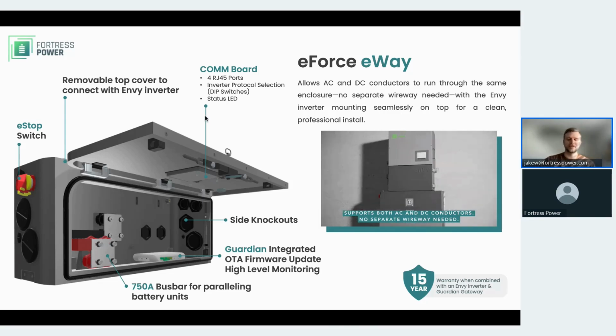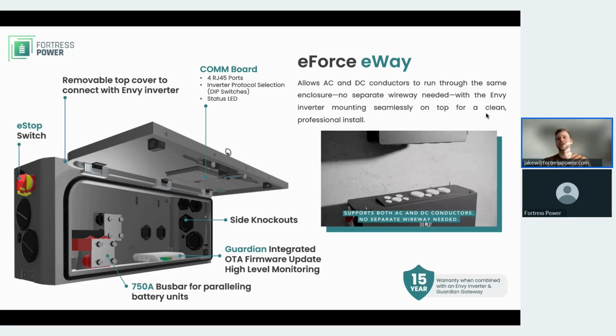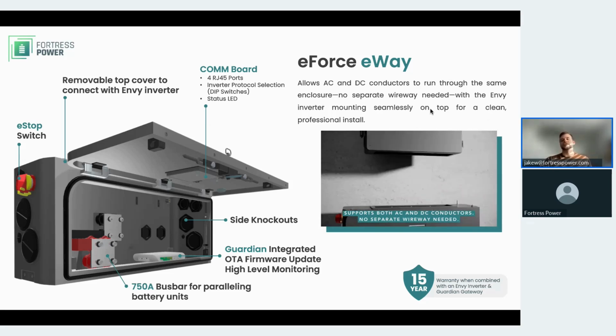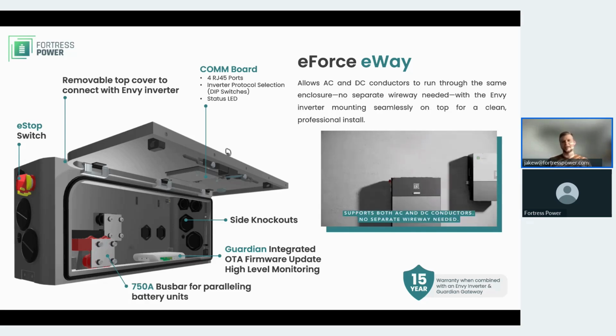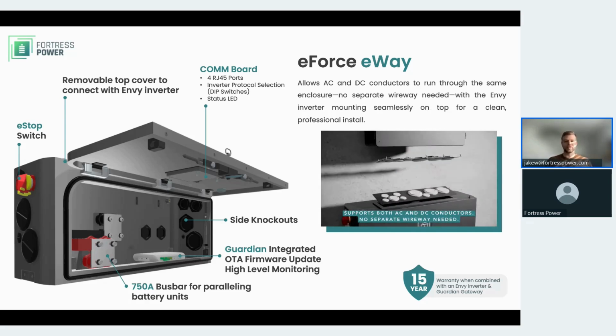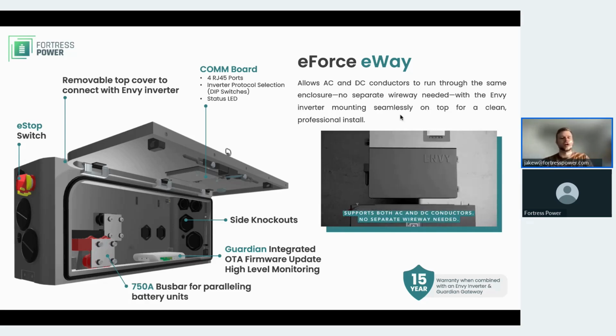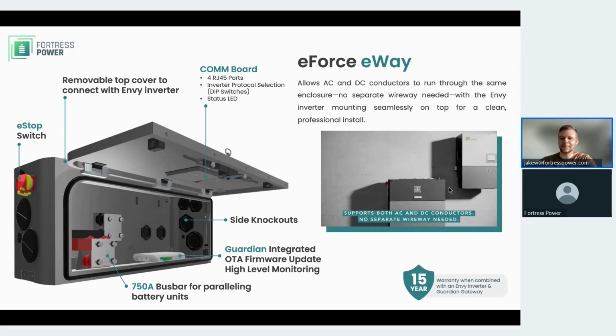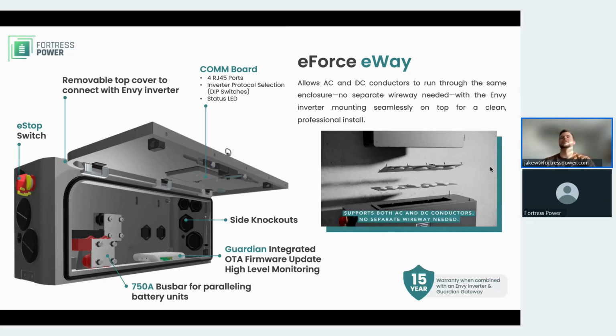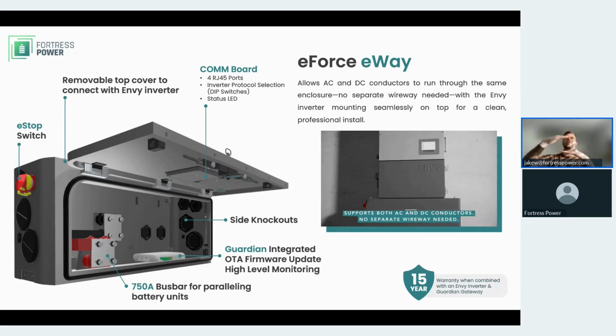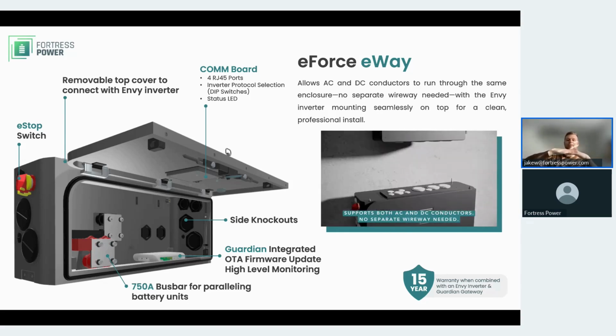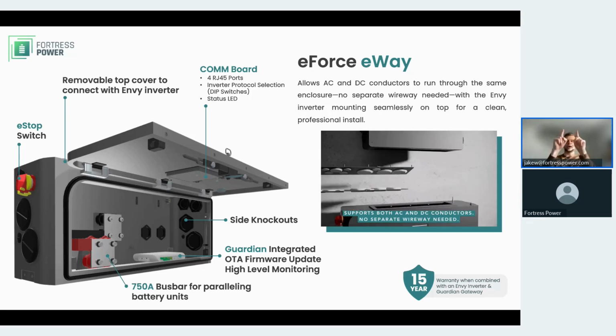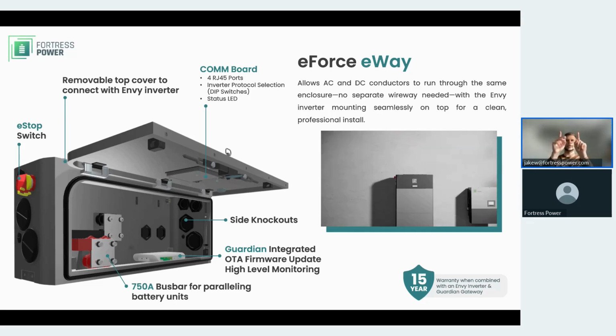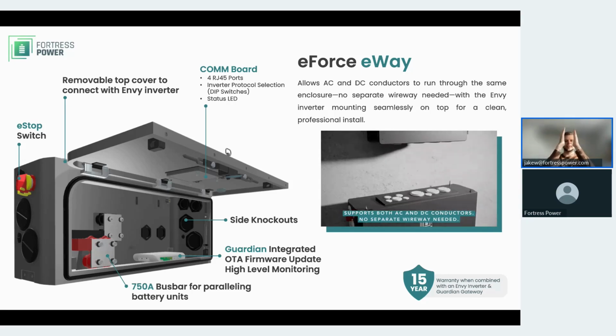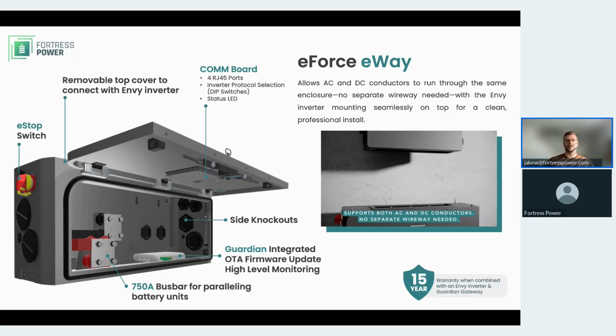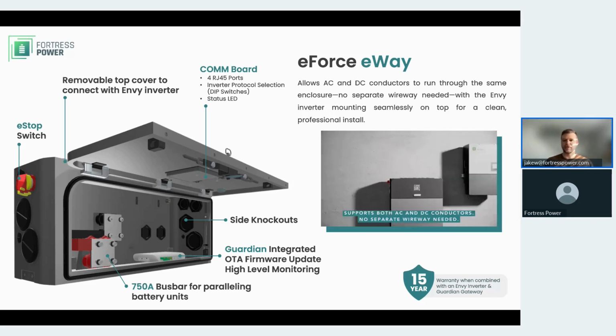And on top of that, speaking of ease of installation, on our inverters there is a bottom plate on the Envy 21, 12, and 8 that can pop off. On top, our eWay has a plate too that can pop off. This allows the inverter and the battery to sit seamlessly on top of each other, so you can drag the wiring, the conduit wiring, and communication cable directly from inverter to battery, putting all the conduit in one place.